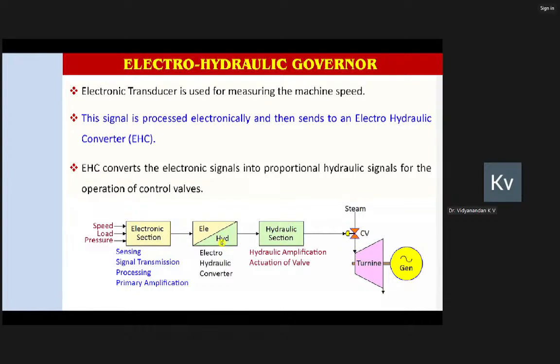And through that hydraulic power amplifier mechanism, we develop enormously larger power or force for operation of the control valve. So the electro-hydraulic governor has two sections: the initial section, which is electronic, with interfacing between the electronics and the hydraulic (EHC), and the final hydraulic section for the operation of the control valves. So in the NTPC case, we have all the 500 megawatt units with electro-hydraulic governor and the hydraulic governor as a backup.